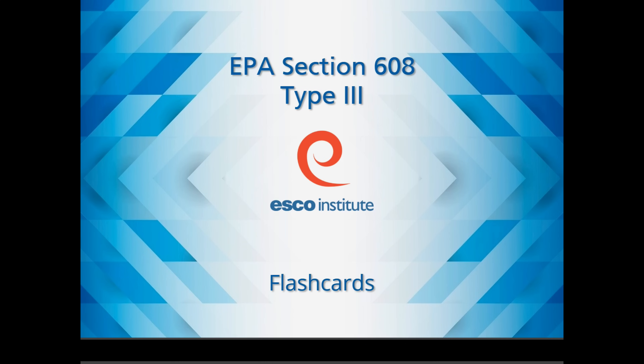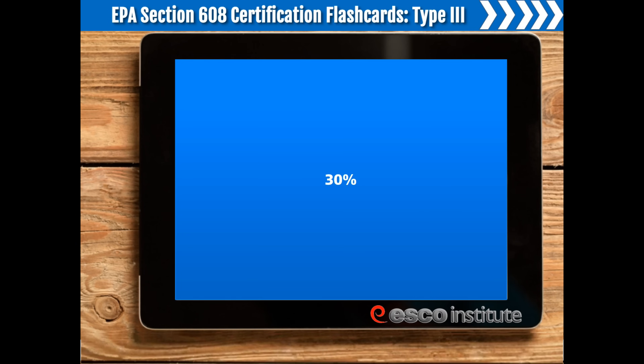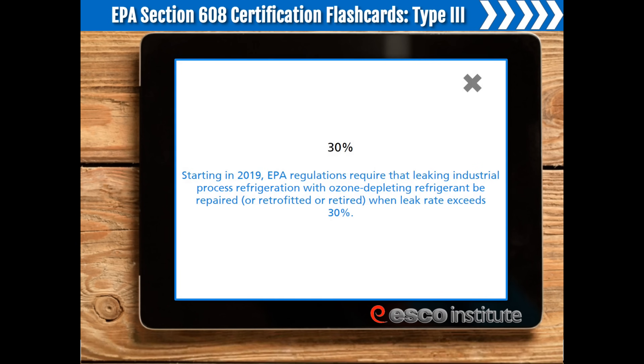Welcome to the ESCO Institute EPA Section 608 Flashcard Program for Type 3 Certification. Please be aware that this is only a sample of the Flashcard Program. The full Flashcard Program is available as part of the ESCO Institute EPA Section 608 Preparatory Course, available at elearning.escogroup.org. 30%. Starting in 2019, EPA regulations require that leaking industrial process refrigeration with ozone-depleting refrigerant be repaired, retrofitted, or retired when the leak rate exceeds 30%.